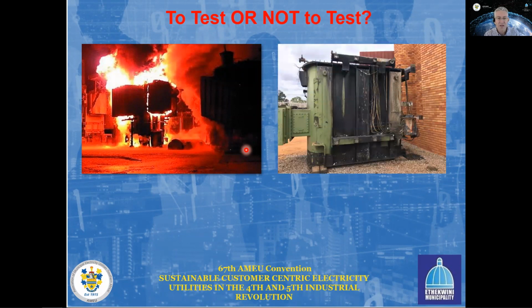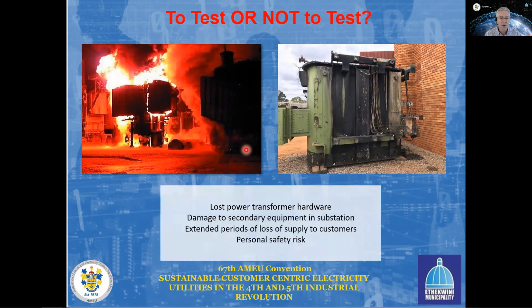Or here, the skeleton of a transformer. Well, it's quite obvious why we don't want this, but obviously we don't want the lost power transformer hardware, which costs millions of rands to replace. A fire like this can result in damage to secondary equipment in the substation, such as neighboring breakers, current transformers, even neighboring transformers, cabling, as well as the relay house in the near vicinity. It obviously will result in extended periods of loss of supply to the customers of a municipality, apart from the personal safety risk that is associated with a fire like this, both to substation personnel as well as fire personnel that are subjected to this.